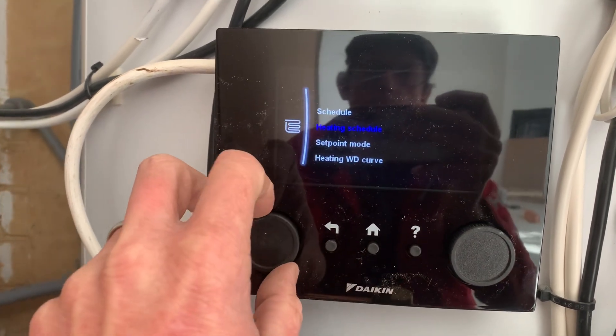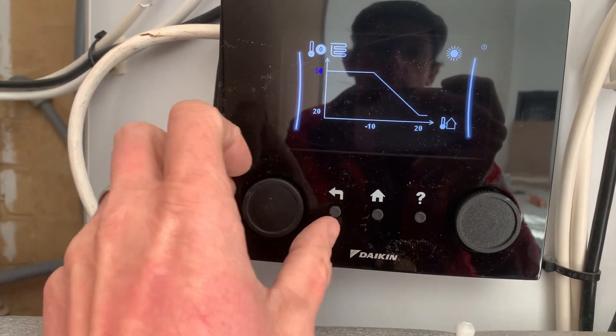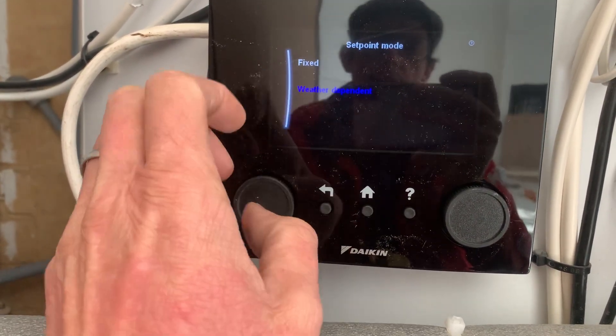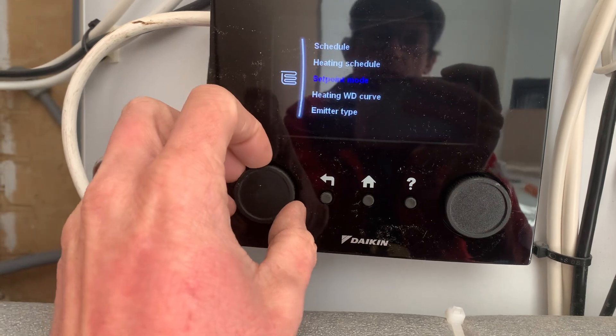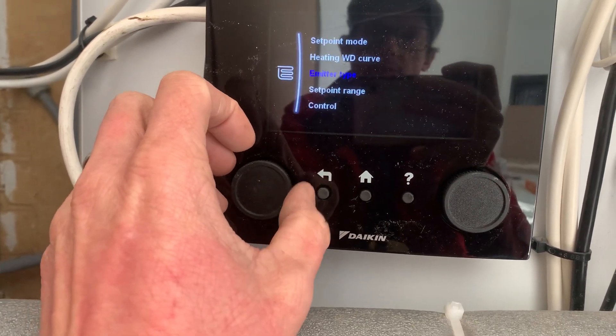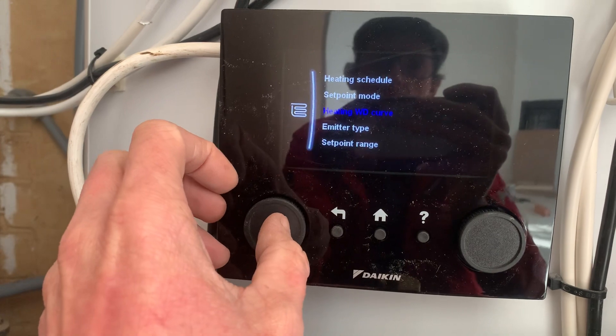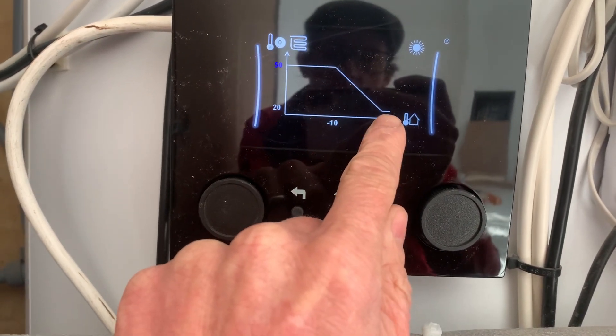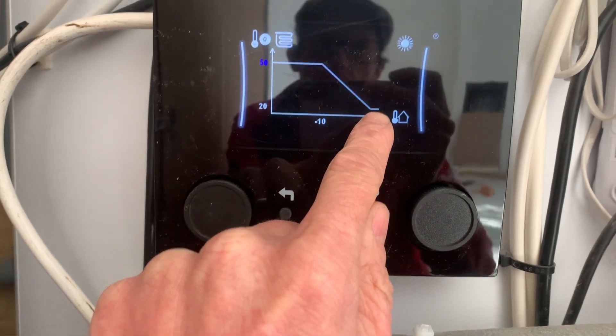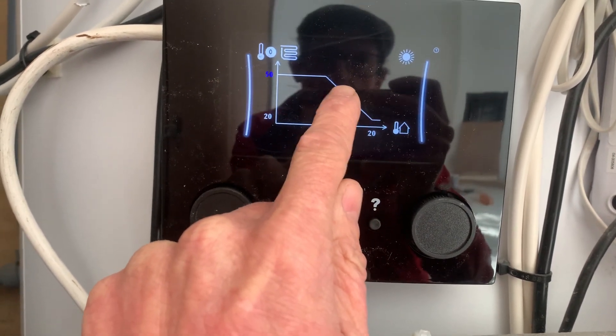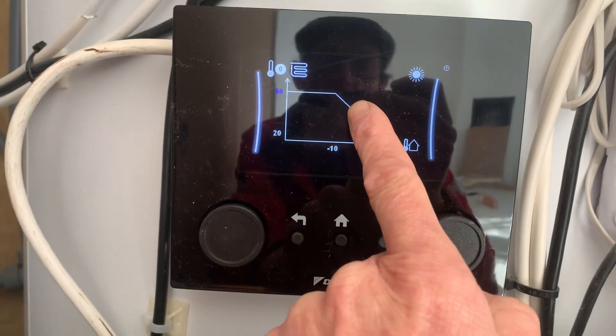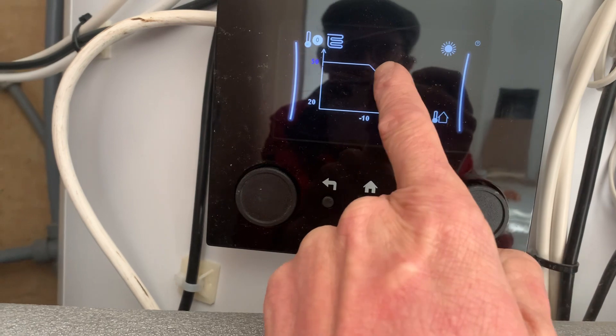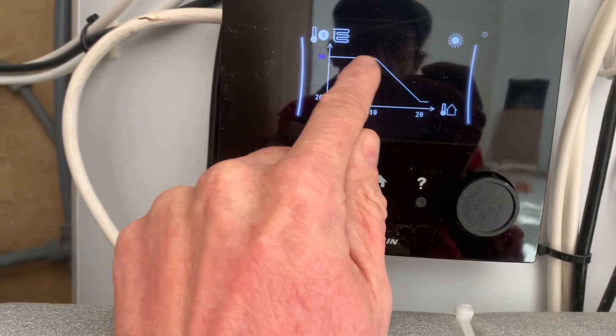If we go to set point mode — weather dependent — weather compensation: so when it's 20 degrees outside it'll run at 20 degrees, and then gradually it'll run hotter and hotter. We're aiming for about 40 odd degrees at the design temperature of minus two, and then when we get to minus 10 outside it'll be up at 50 degrees.